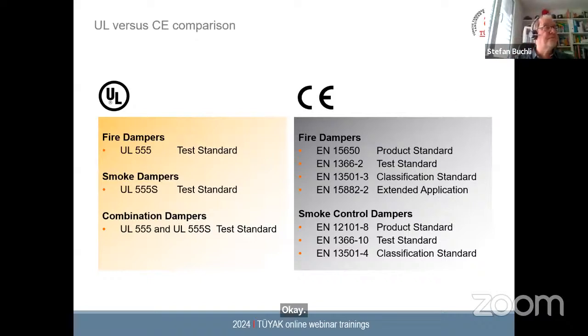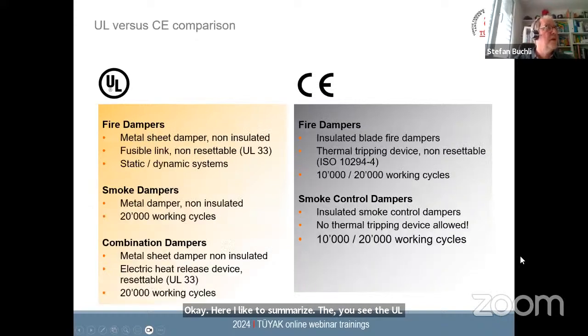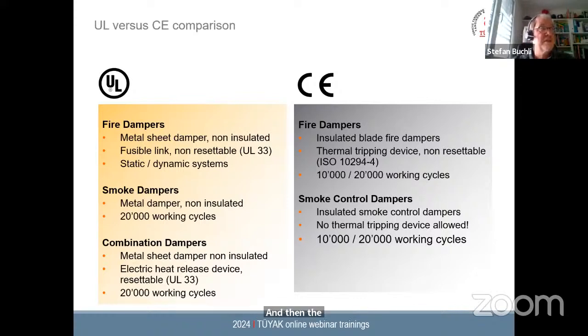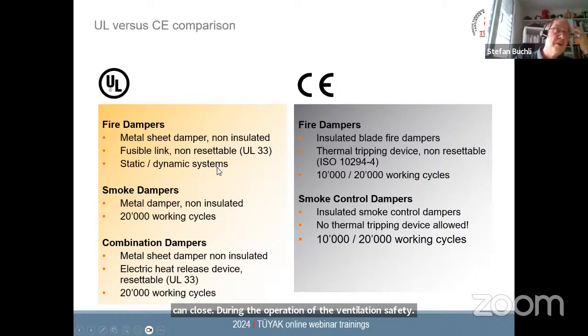Here I like to summarize the comparison. You see the UL standards on the left-hand side, the CE standards, as I showed you, on the right-hand side. Then you see some of the differences. You noted that on the UL side, fire dampers are always metal sheet dampers, non-insulated. They have a fusible link, non-resettable. There are different types of fire dampers for static or dynamic systems. That means static systems, you have to switch off the ventilation system first, and then the damper closes. And dynamic system, the dampers can close during the operation of the ventilation system. That's also special. That's something we don't have on the European side.